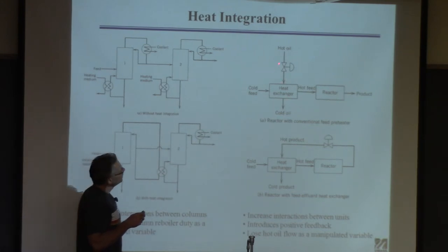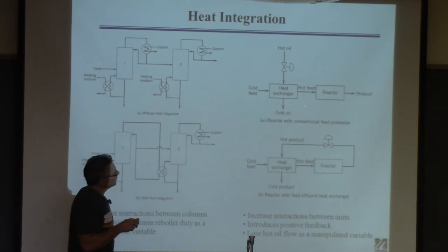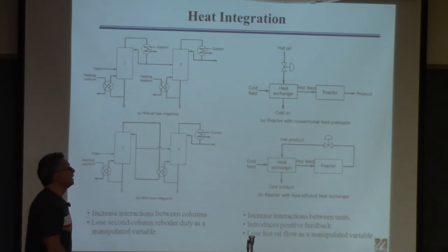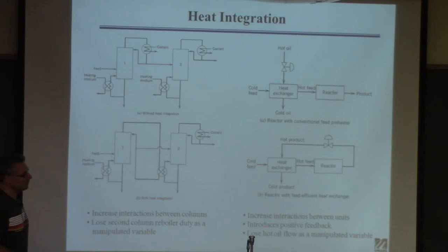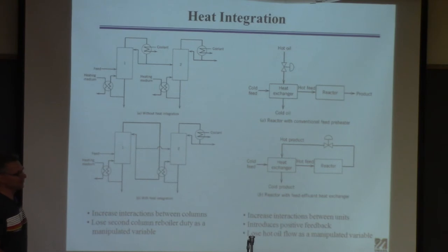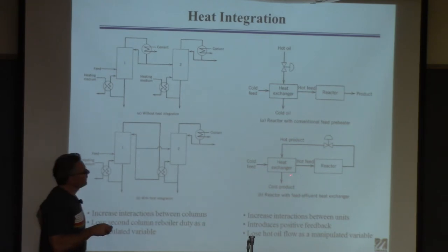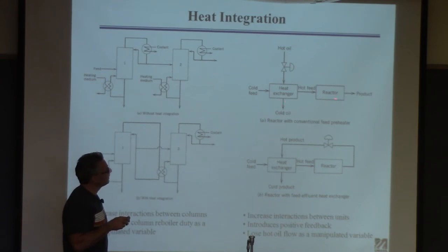Here's another example. You're trying to heat up feed for a reactor, so you put the cold feed through an exchanger with some heating oil to produce the product. If this is an exothermic reaction, the product stream is quite hot. Maybe one should take this product stream and use that to heat up the feed instead — this should ring bells. You take the product stream, use it to heat the feed, cool the product, and heat the feed simultaneously, saving energy both for heating and cooling downstream. From an energy perspective, this looks obvious, but from a control perspective, it could be problematic.